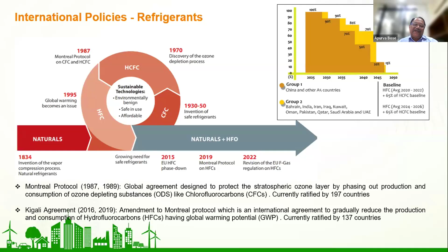Coming back to refrigerants: HCFC, as we know, is going to be phased out. It has already been phased out to a great extent, but formally by 2030 it should be totally phased out. Even HFC phase-down has already started. For us, the target is 85% reduction by 2047, and I believe we are probably well ahead of that curve at present. We also have HFOs, which have lower GWP and lower ODP.